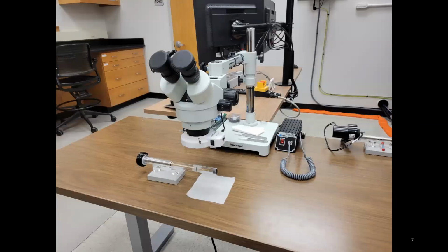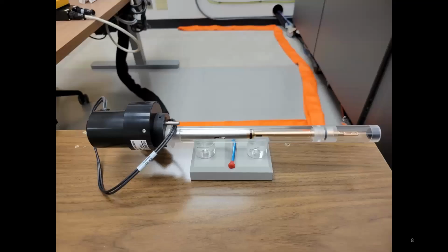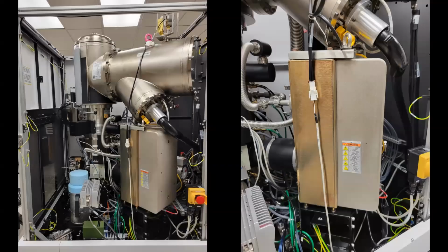So this is a sample prep station. We've got vacuum tweezers, a little microscope so you can check out what you're doing. This is the single tilt, so it doesn't actually really do anything. We'll show you in a second. This is the double tilt holder. This one has a tiny little arm here. And so this guy can tilt like this, 60 degrees, which is actually pretty good. You can do a lot of stuff with 60 degrees. In fact, when we get into holography and all that kind of stuff, this double tilt holder will do what we need it to. So, okay, the vacuum system.